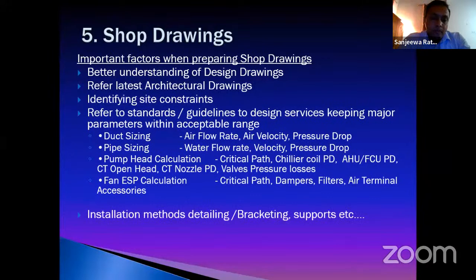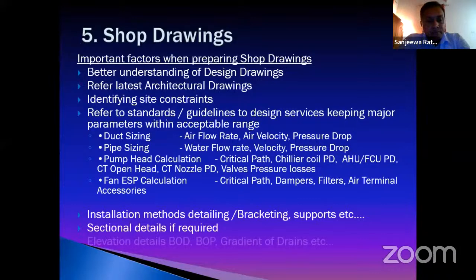Then the installation methods also. In the shop drawing, the contractor must mention how it's going to be installed, with bracketing and supporting details. Sectional details should also be provided if required, for example showing the level of the duct inside the ceiling, and if it's going to clash with other services, how we are going to avoid it. These things must be shown as sectional details, including elevation details like bottom of duct, bottom of pipe, and for a drain pipe, the gradient.